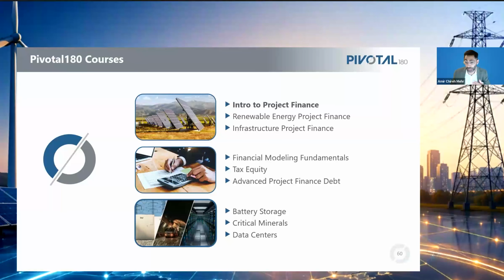But battery storage systems, to make a really bad joke, but an honest joke, right? The rules of thermodynamics, if you've ever studied physics, some smart aleck professors will summarize as the first rule is you can't win. The second rule is you can't break even. And the third rule is you're going to lose. And that's a long-winded way of saying that of the 100 megawatt hours we purchased, about 20 megawatt hours is going to be lost in round trip inefficiencies. So you can only sell 80 megawatt hours to the grid, right?